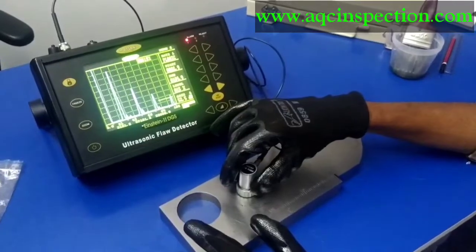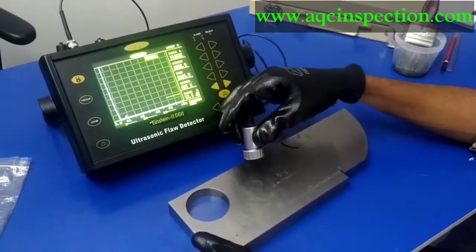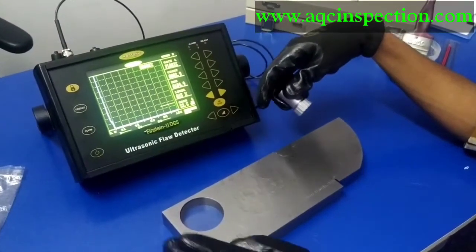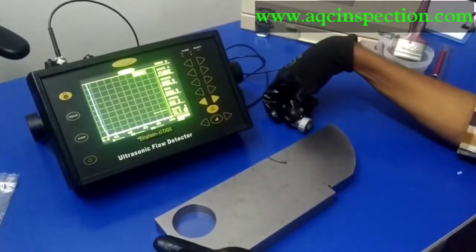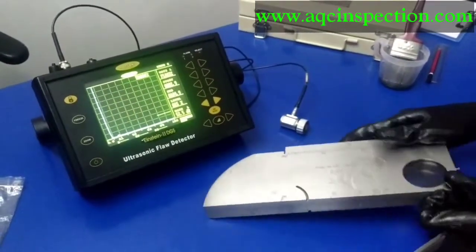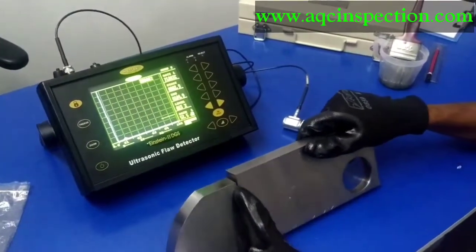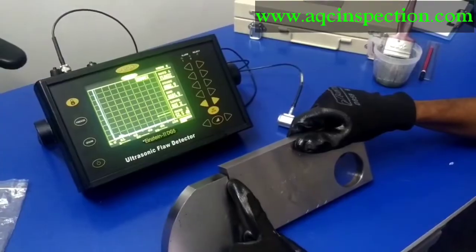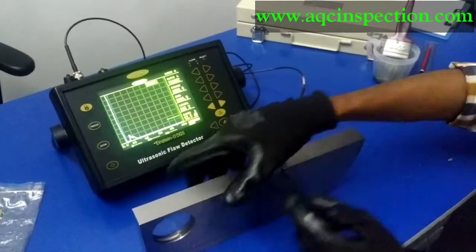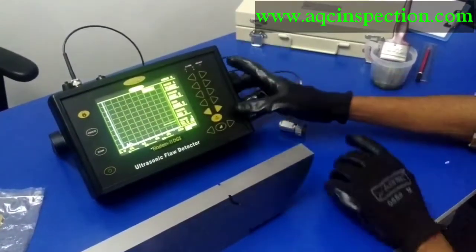This is the normal calibration using a V1 block but there are several steps to it like checking the vertical linearity, resolution, sensitivity and so on. So let me do the resolution check right now. Which is, as you can see, this is the notch right here, 5 mm gap. So I am going to be placing the transducer on top of here, right here to get this signal in my screen.